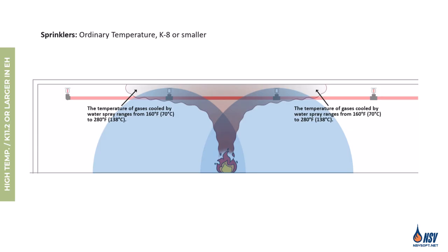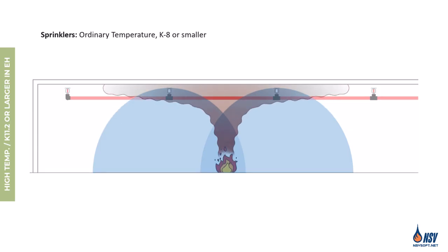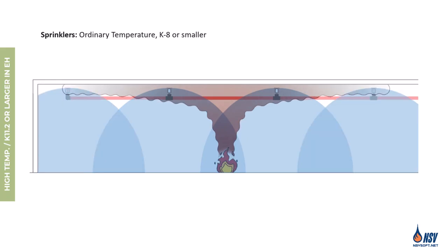This level of heat, carried by the ceiling jet, is still sufficient to activate sprinklers located farther from the fire source. Activation of these distant sprinklers increases the overall flow rate in the piping network. This elevated flow leads to greater pressure loss, reducing the available pressure at sprinklers near the fire. As a result, those critical sprinklers discharge less water, compromising fire control effectiveness.